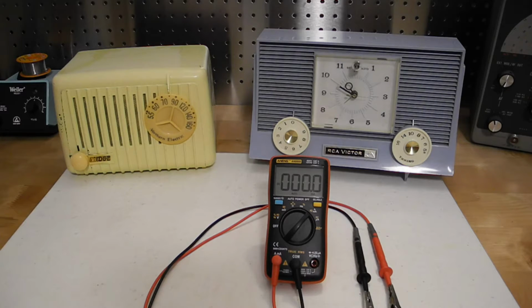Generally, to cause harm such as cardiac arrest, stopping the heart, requires a certain level of current. Some very approximate ranges of current and their effects are the following, and these assume alternating current. 1 milliamp, or thousandth of an amp, is about the lower threshold of sensation. About 5 milliamps is considered the maximum harmless current. 10 milliamps is the threshold of painful shock and the point at which one may not be able to let go. At 20 milliamps, breathing may cease due to lack of muscle control.